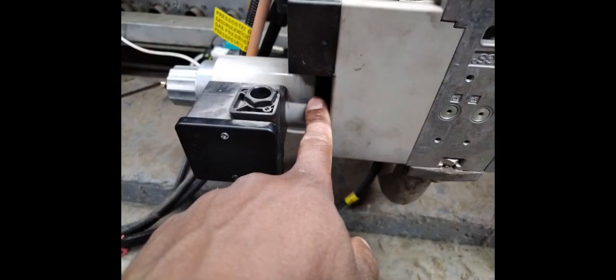Then I made an adjustment to my first stage, which is here. You have to remember to be very precise when making adjustments to gas valves or making any sort of adjustments to gas appliances. It's good to use a pen and mark where you started off from and to make gradual increments, giving the flue gas analyzer a chance to pick it up and also your manometer.